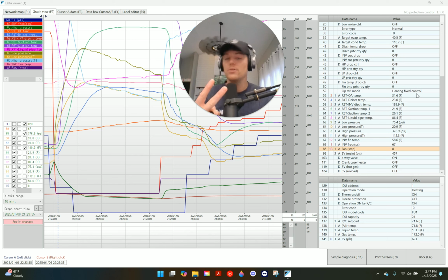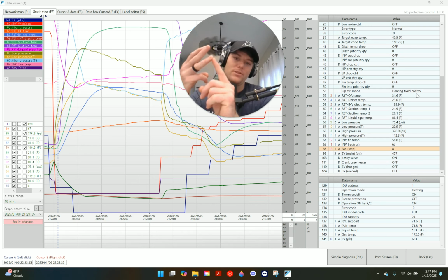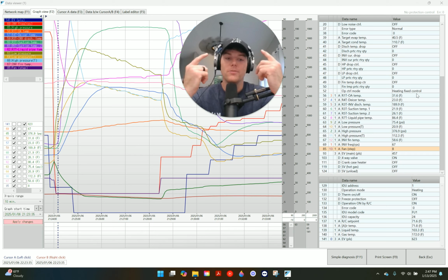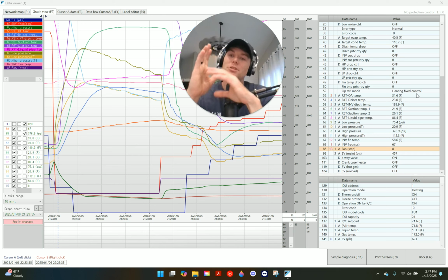Maybe this unit doesn't have a subcooler. Okay, I skip that step. I go to the next set of data. Okay, what's going through my liquid line? It's going to another expansion valve for my outdoor heat exchanger that's now an evaporator. Okay, what are those valve pulses? What is my temperature before and after that valve, right? There's another 5 things. Go through that through the entire data set. And if I don't have anything there yet, nothing has triggered my brain to say that's a problem, I'll just move on to the next.